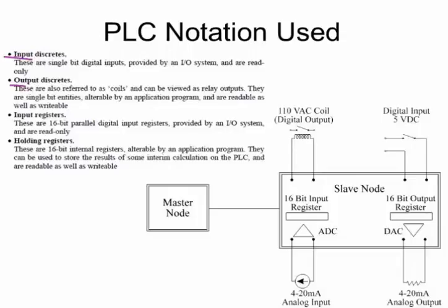If you go to your Allen Bradley PLCs, it's your I: file, your input. It's the direct card reading inputs. You cannot write to these. They are read only in a PLC space. So your input register is a read-only 16-bit integer. Generally that's coming from the field, though it depends on the manufacturer and how they've configured it.